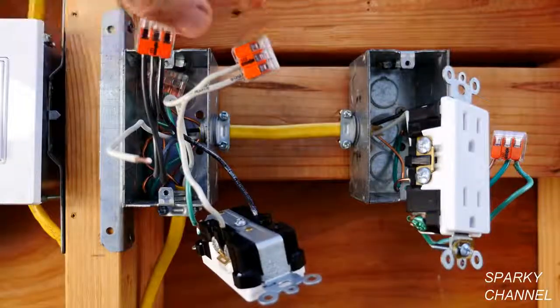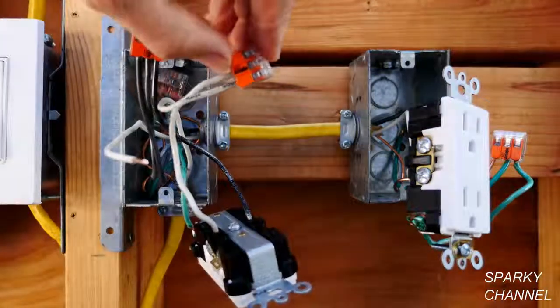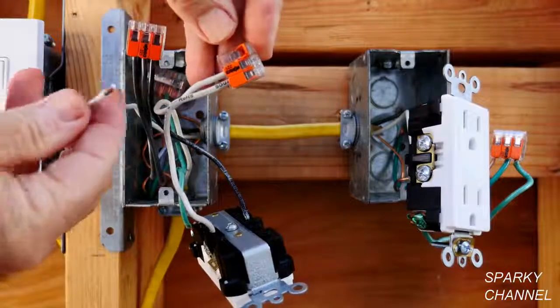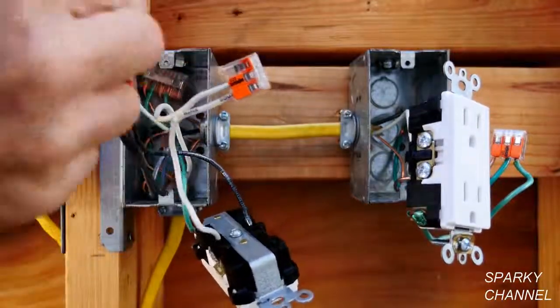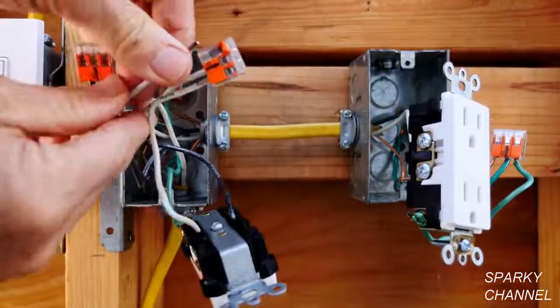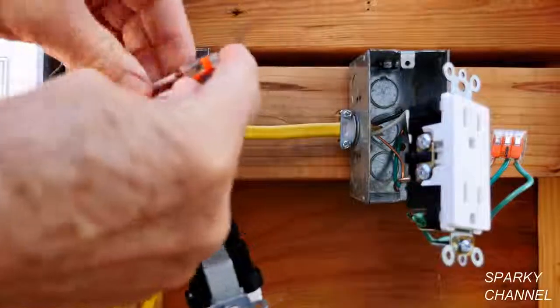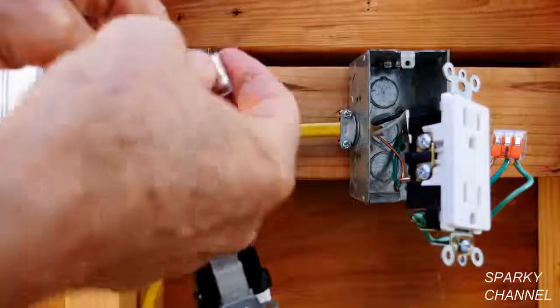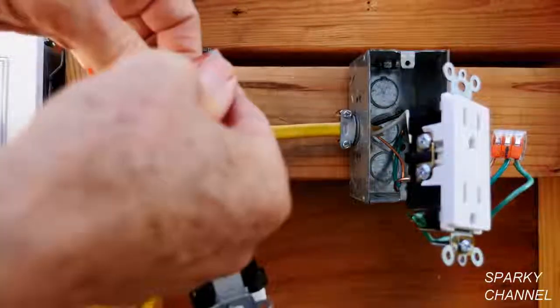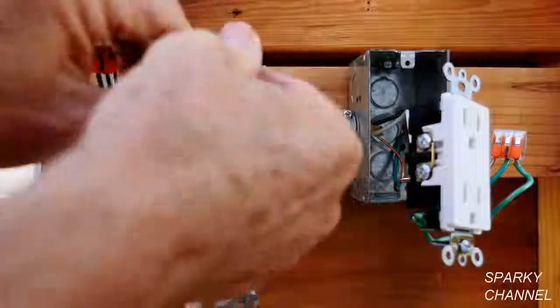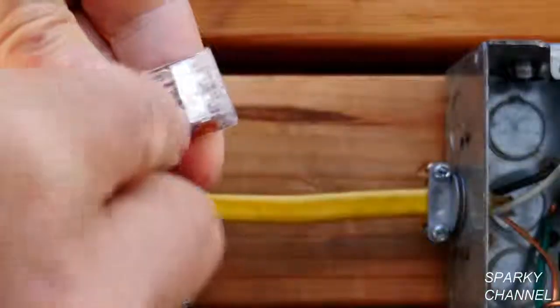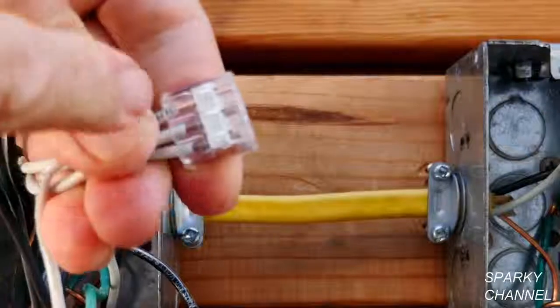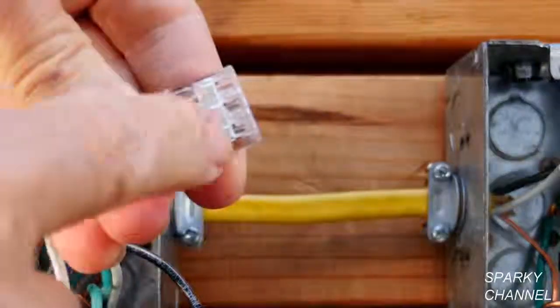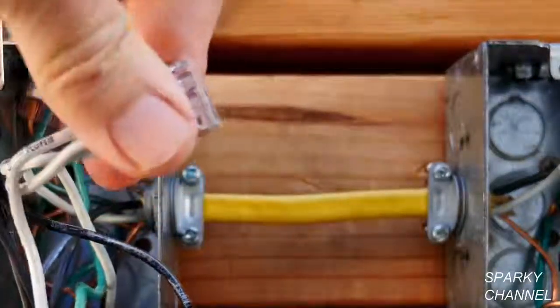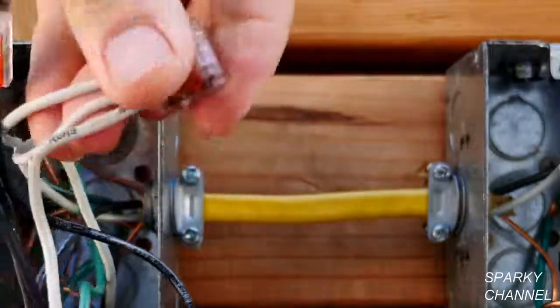Since there's Wago lever nuts connecting these wires, all we have to do is open up a slot, put the wire in the Wago lever nut, clamp it down. Give it a nice tug and make sure it's connected. You can turn it around and you can see it's clear back here, so you can see that all three of the neutrals are in the connector very well.